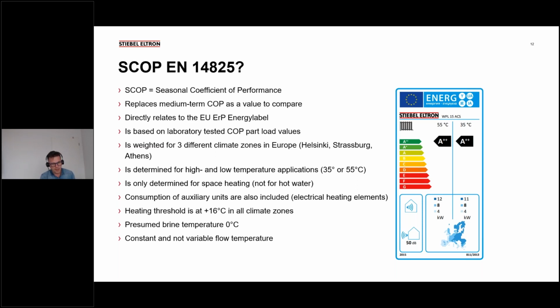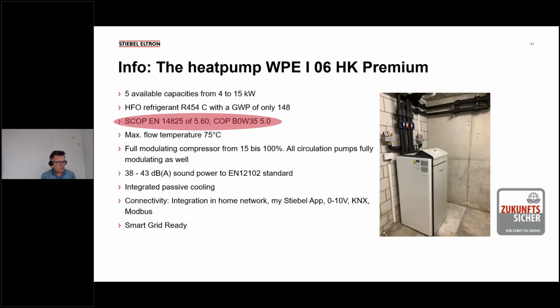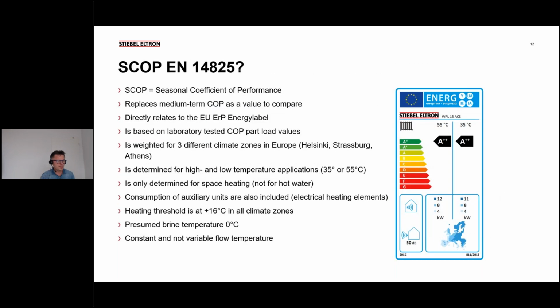So I use the Strasbourg climate for my location here. And as you saw before, the heat pump has 5.6 SCOP, related to the Strasbourg climate. It's only for heating, not for domestic hot water. You see a couple of pieces of information here that are used to determine the efficiency. This 5.6 is always calculated with a brine temperature of 0 degrees, which is actually pretty low.